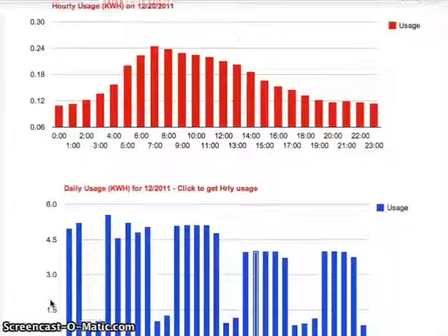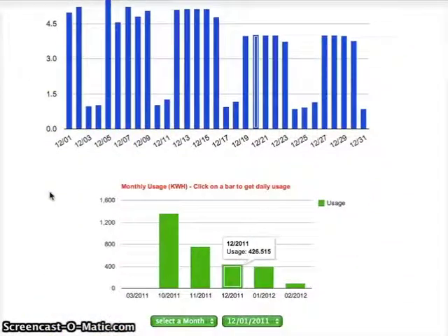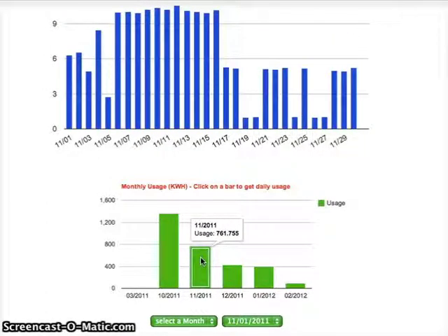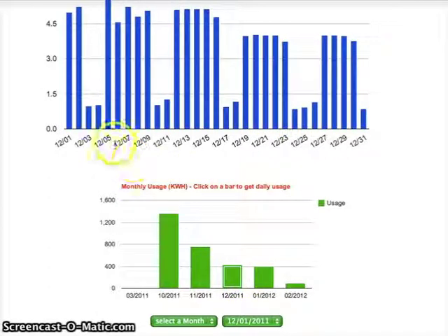For Step 6, you might want to use the monthly and daily usage plots to look for any gradual or abrupt changes in electricity usage. Here, you can see that between November and December of 2011, the usage went from being very irregular in November to following a regular weekday-weekend pattern in December. This might signal a change in how occupants are using the facility.